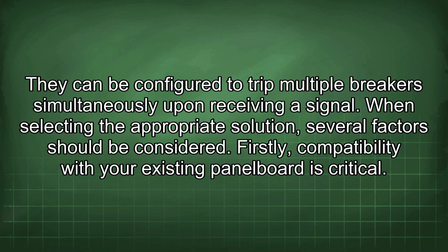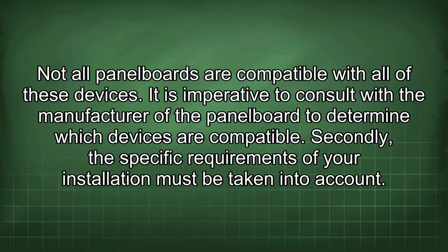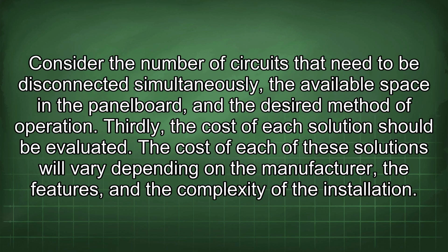When selecting the appropriate solution, several factors should be considered. Firstly, compatibility with your existing panel board is critical. Not all panel boards are compatible with all of these devices. It is imperative to consult with the manufacturer of the panel board to determine which devices are compatible. Secondly, the specific requirements of your installation must be taken into account. Consider the number of circuits that need to be disconnected simultaneously, the available space in the panel board, and the desired method of operation.